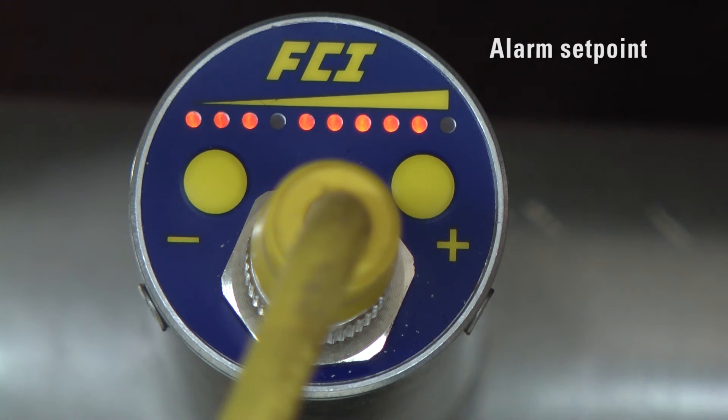After 5 seconds, the LEDs will signal an acknowledgment that the settings were valid and assume normal operation. The flashing LED indicates the alarm setpoint—it flashes quickly when in the alarm state and slowly under normal conditions. It's a quick way of verifying the fail safe is set as intended.